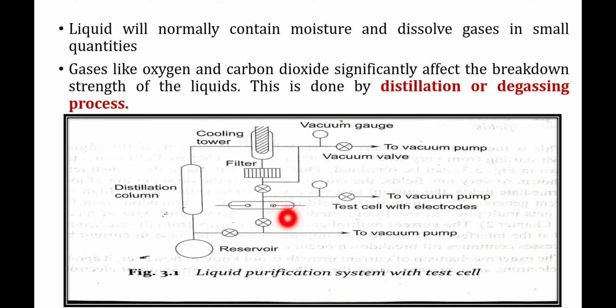Why are we providing this low voltage for the breakdown test? Because the distance between the two electrodes is very small. That is why we provide a voltage of 50 to 100 kV. In that case, the breakdown strength obtained in pure liquids is very high, of the order of 1 megavolt per centimeter, and the conductivity is of the order of 10 raised to minus 18 to 10 raised to minus 20 mho per centimeter.